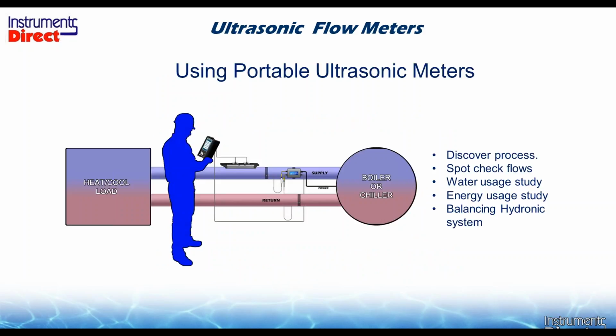So a traditional energy loop, what is it? Well, a hydronic system is basically a closed loop, and we're going to generate either heat or cold from the load, and it's going to be transferred through this loop to a boiler or chiller. So look at this. It is a closed circuit. So first off, if you want to monitor flow in such a system, you only need to monitor the flow on the supply side, or the return side if you prefer, because the gazinta equals the gazouta. So we can monitor flow on the supply. And then if we wanted to add energy to the recipe, we would add temperature.